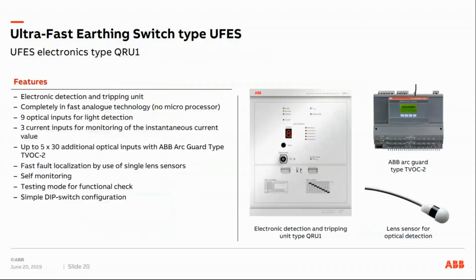Having a look at the 2 control units, here we can see the QRU1, which is a detection and tripping unit within one device. It's completely analog technology, so there is no microprocessor. It has 9 optical inputs for light detection and 3 current inputs for the monitoring of the instantaneous current value. In combination with ABB's Arc Guard type TVOC2, it can have up to 150 additional optic inputs, and that needs for the fast localization 1 single lens sensor.